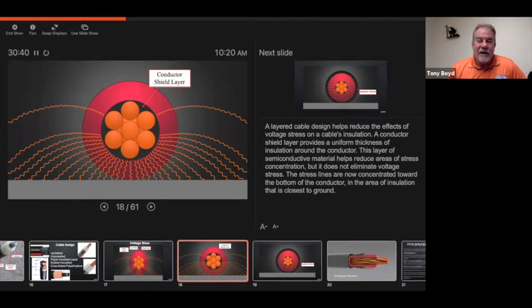There is some current leakage across insulation, any insulation. When it is energized, we'll have some current leakage, and cables, your booms on your bucket trucks, your hot sticks, your shotgun sticks are all designed for this current leakage. It's very, very small. If we got a measurement on it, a lot of times it's so small that it would take a microamp meter to actually get a reading on it. But yes, it does allow some leakage, and the whole purpose of that conductor shield layer is to make that leakage even. And so the stress lines are now concentrated toward the bottom of the conductor in this picture.